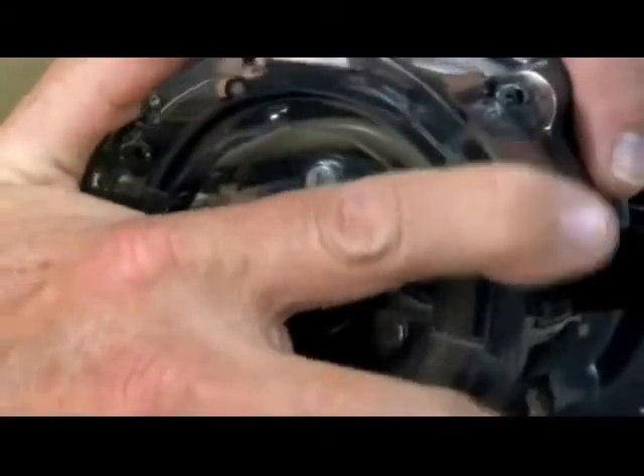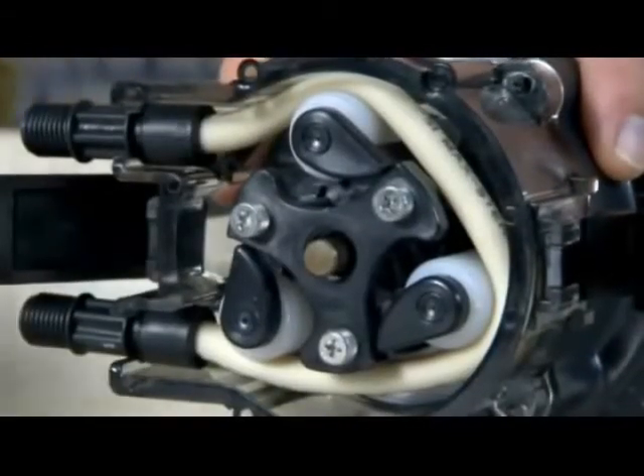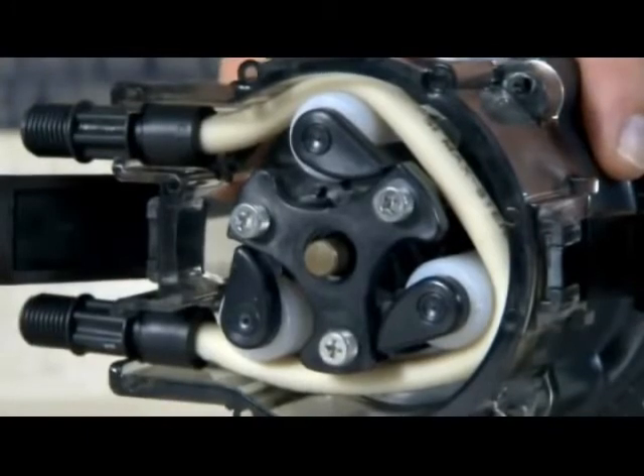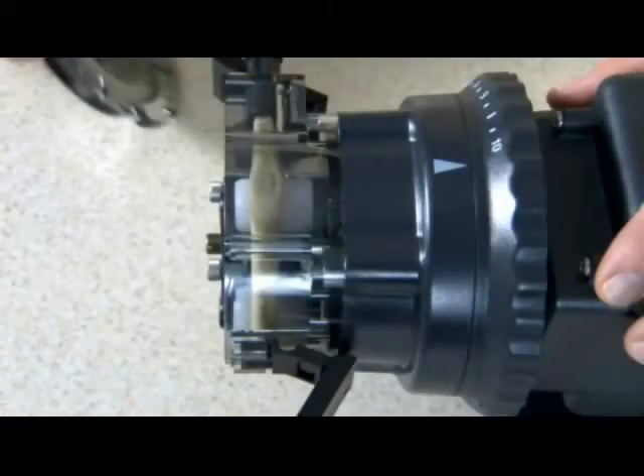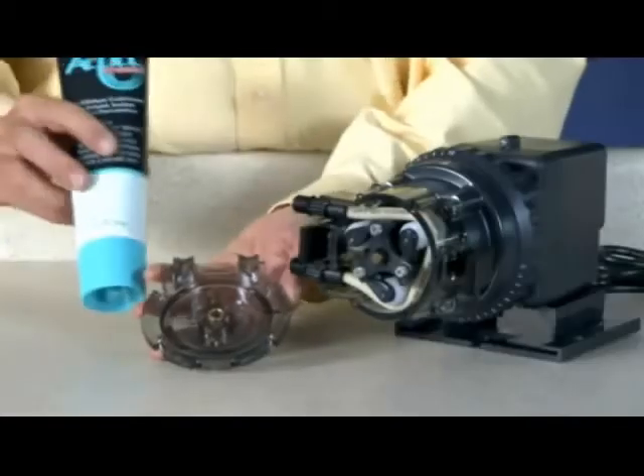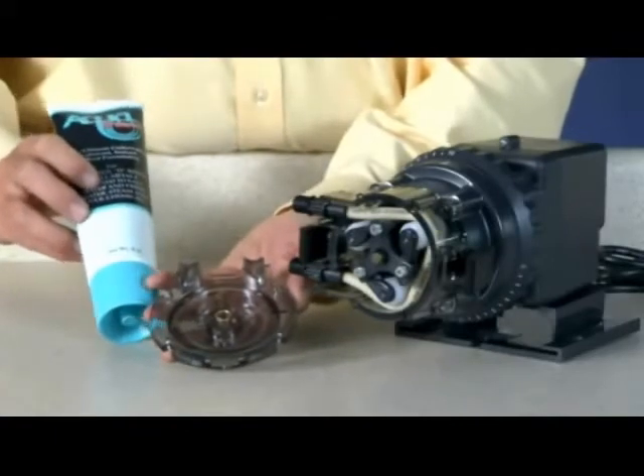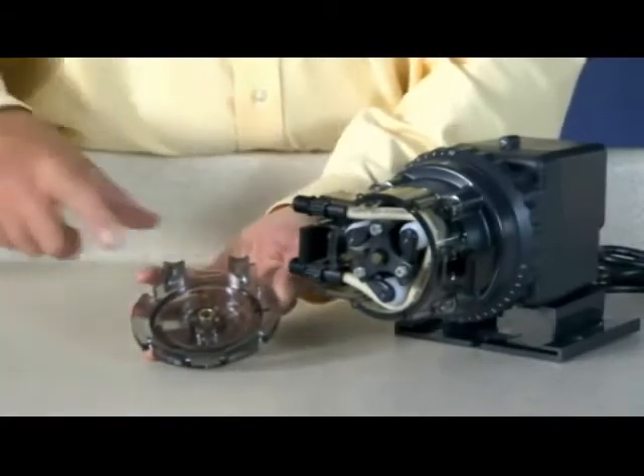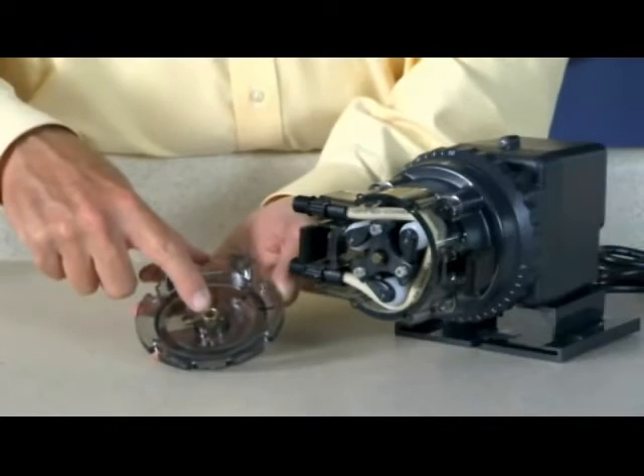Hold the feed rate control securely. Use the cover as a wrench and quickly snap. Rotate the roller assembly clockwise to expand the roller assembly. The tube will be pressed against the tube housing wall. Apply a small amount of Aqua Shield to the cover bushing only. Do not lubricate the pump tube.